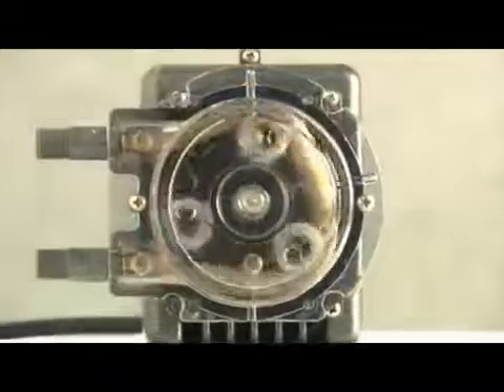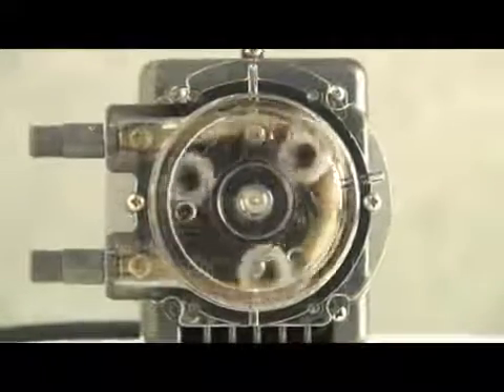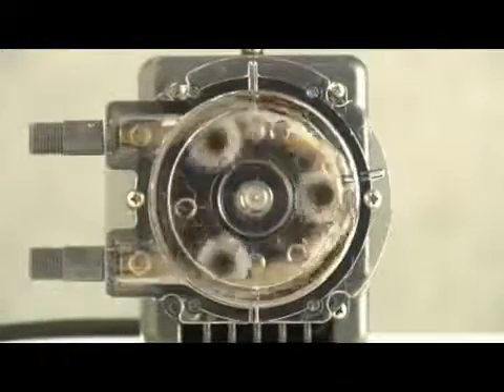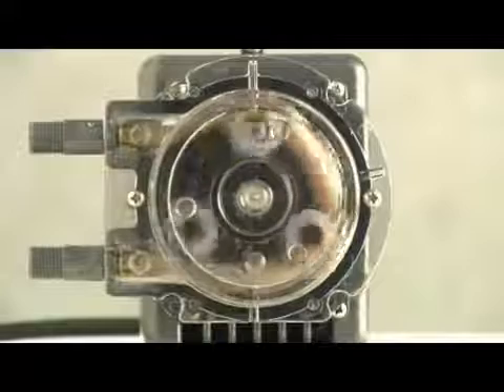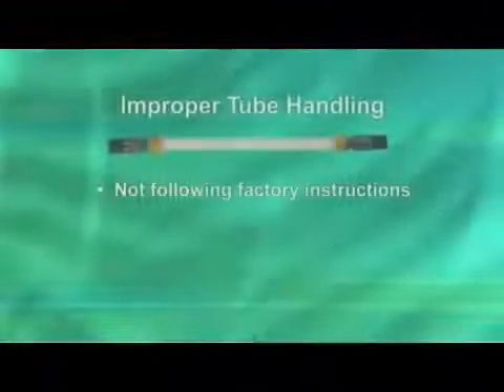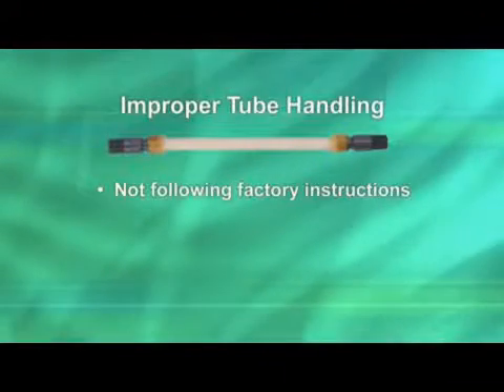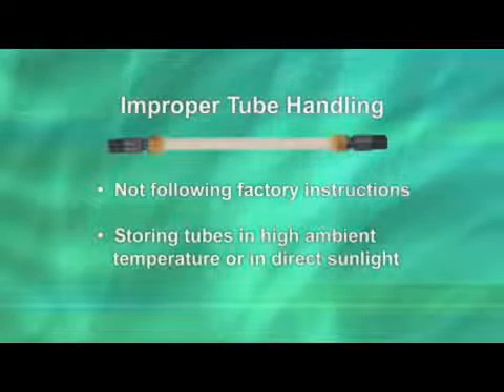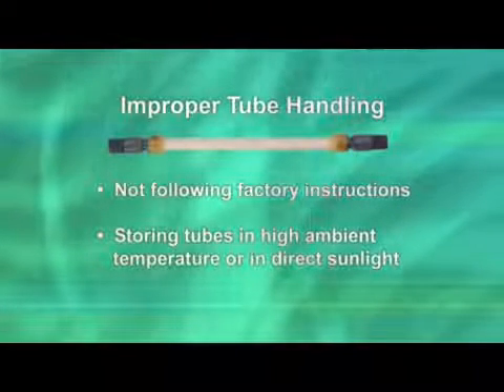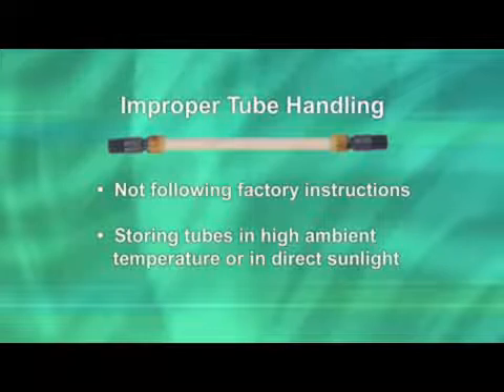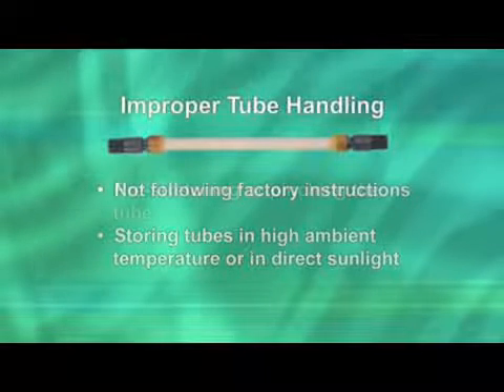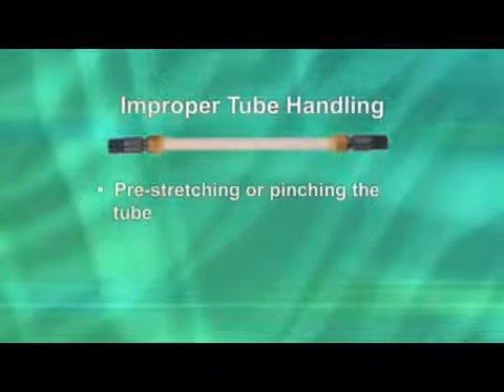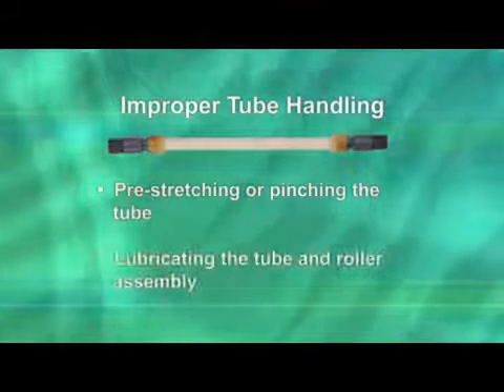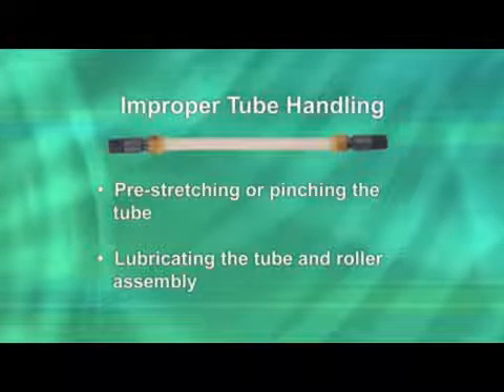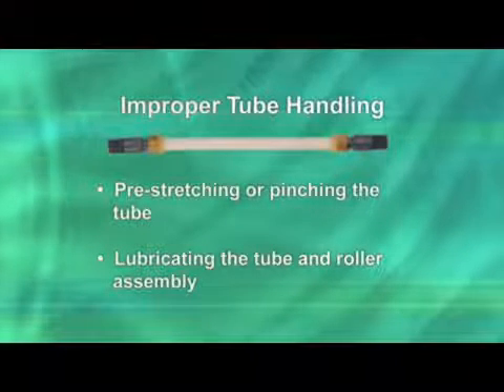Tube leakage around the gray fitting and/or fitting pulling out of the tube or other tube malfunctions are most commonly caused by mishandling the pump tube. Some examples are not following factory tube replacement instructions, storing tubes in high ambient temperatures or long-term exposure to direct sunlight weakens the tube material. Prior to installation, pre-stretching, lubricating the tube and/or roller assembly, or pinching during installation compromises the tube material.